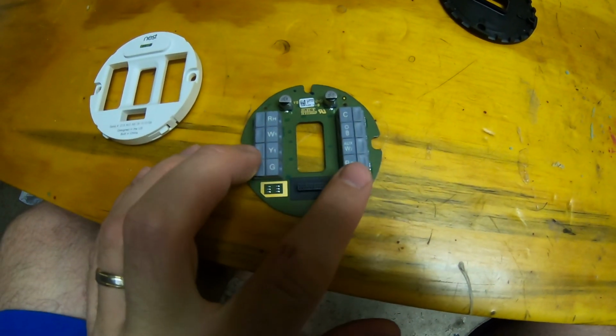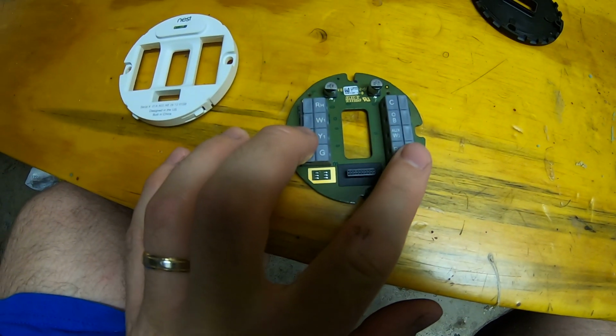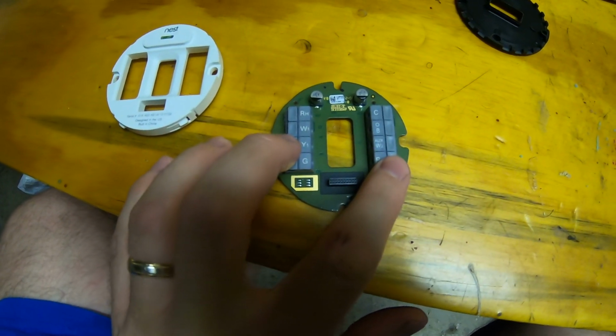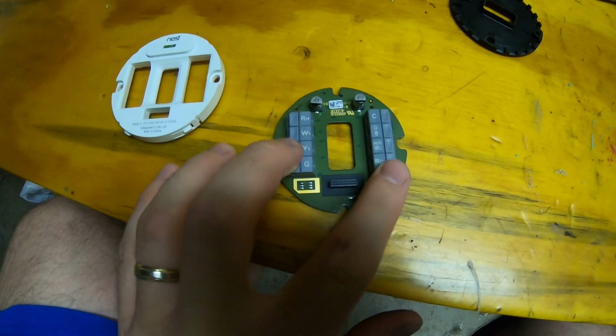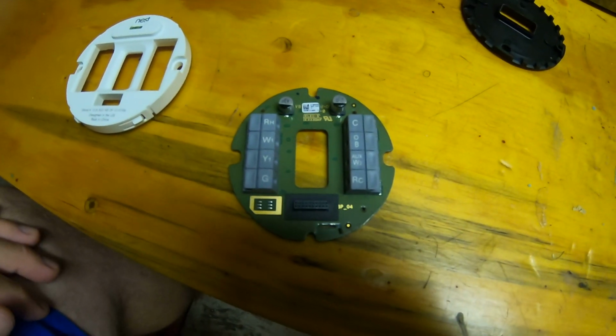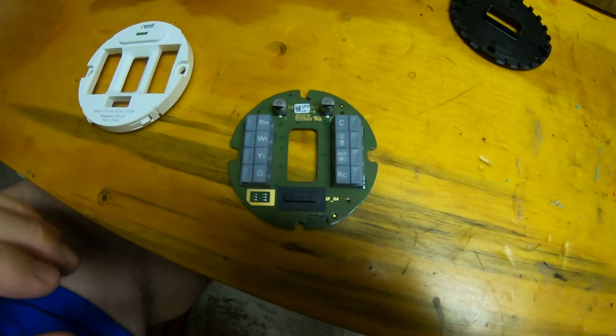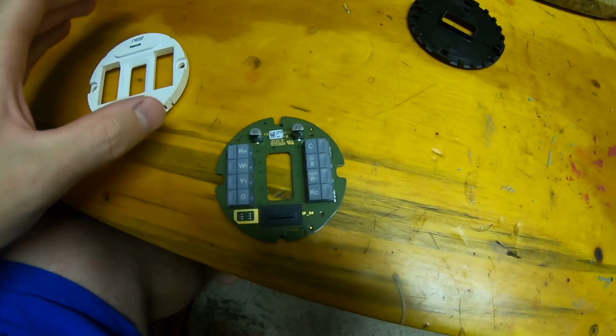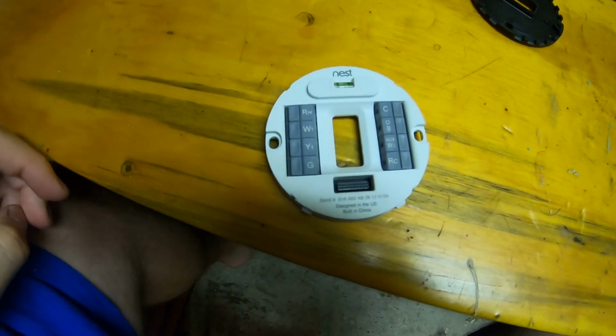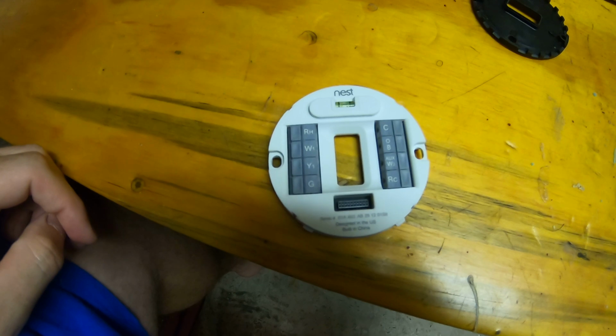But again, if you jump R to Y1 for cooling, and you get 28 volts, or 24 to 28 volts at the contactor, that's a pretty strong indication there's a problem with the Nest, either in this backing plate or perhaps with the actual Nest itself. So hopefully that helps somebody.